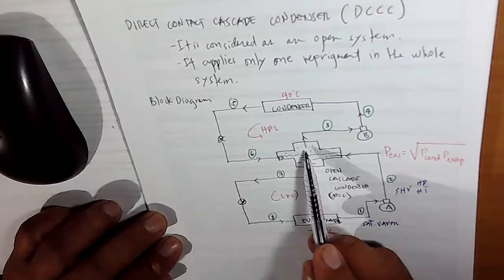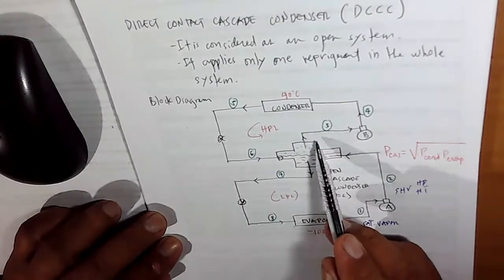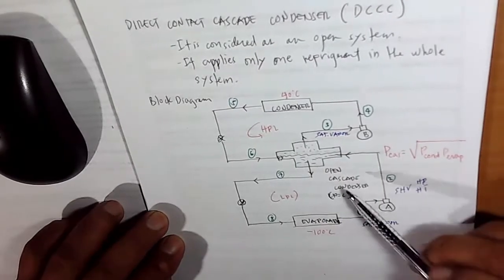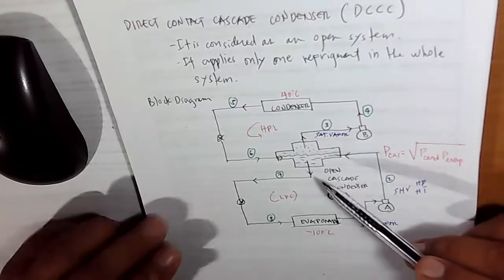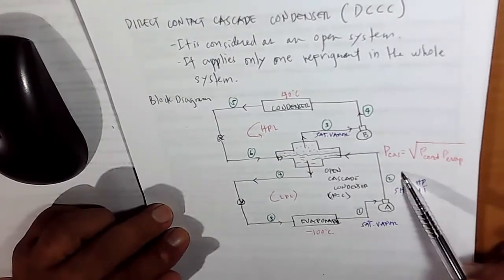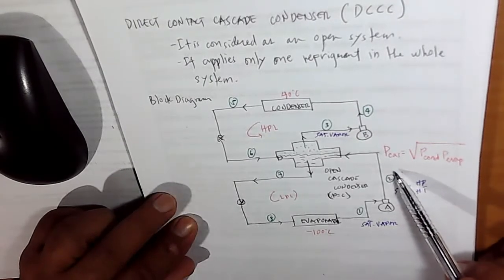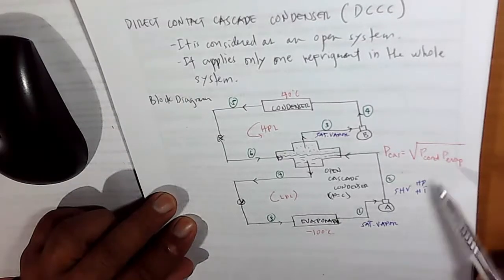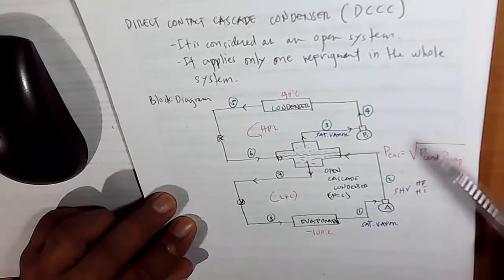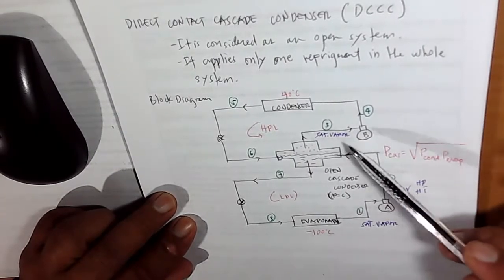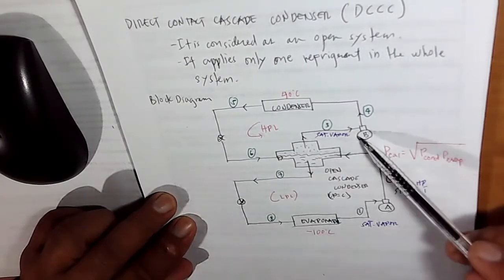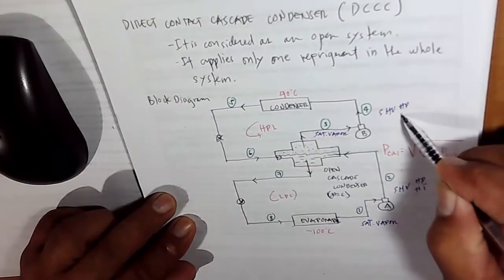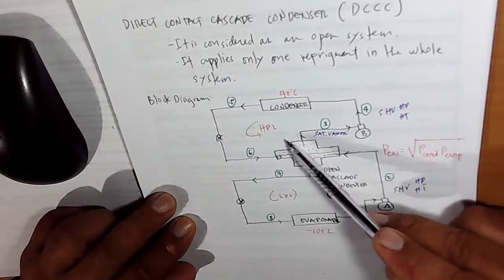Upon its exit from the cascade condenser, at point 3 it is once again saturated vapor. The pressure at this point corresponds to your cascade condenser. If the cascade pressure is not given, the pressure of the cascade condenser is equal to the square root of the condenser pressure multiplied by the evaporator pressure. The saturated vapor, whose pressure corresponds to the cascade condenser, will go to your compressor and be compressed once again, converting it into superheated vapor — high pressure, high temperature — at high pressure loop condition.